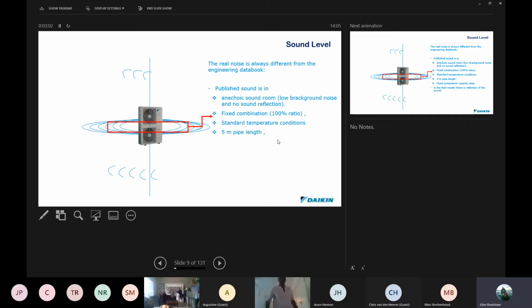measure their sound? Well, real noise is always different from the engineering data books. So inside our engineering data books, remember we spoke about data books in the first session. Okay, you'll see that there's values given there for sound, and it's published in an anechoic sound room. That's a room with low background noise and no sound reflection. Have you ever seen one of these or been in one? You'll know that they've got foam padded walls that looks like egg crate type material. Okay, and this deadens out the noise so that you only get the noise from the unit.